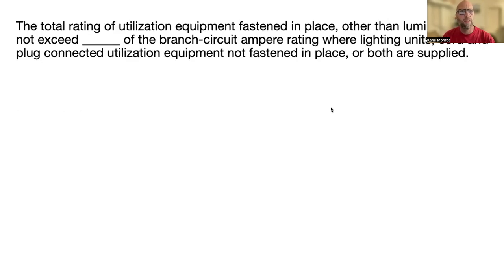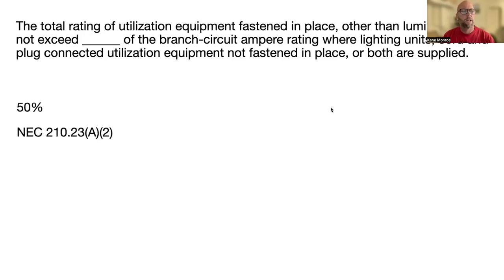The total rating of utilization equipment fastened in place, other than luminaires, shall not exceed blank percent of the branch circuit ampere rating where lighting units, cord and plug connected utilization equipment not fastened in place, or both are supplied. The answer is 50 percent — NEC 210.23(A)(2).